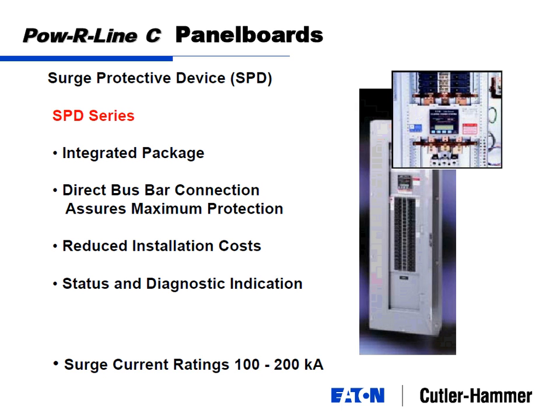And of course, what gets most damaged by transient overvoltages? Our laptops. If you got a process with a PLC, those can get damaged, and all of a sudden you're running a process with $1 million batches of chemicals you're mixing. Your transient overvoltage takes your PLC out, shuts down your process, caused by the Xerox machine, and you have to dump $1 million worth of scrap because you weren't smart enough to put in a $2,000 unit like this.